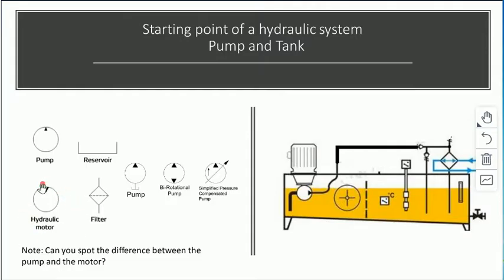Hydraulic motors are very, very powerful. To give you an idea, the size of a single phase or a DC motor for a certain amount of power, let's say 1 horsepower, is 10 times bigger than a three phase motor. And a hydraulic motor can be 10 times smaller than a three phase motor. So compared to an electrical DC motor or a single phase AC motor, a hydraulic motor only needs to be about 1/100th of the size. That's a rule of thumb calculation, but that is quite amazing with the amount of torque that can be produced. They are really, really powerful, and that's one reason why hydraulic motors are so much favored, and why they're used very often in industrial systems.